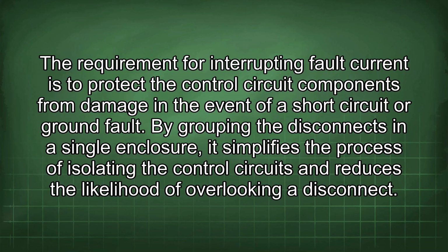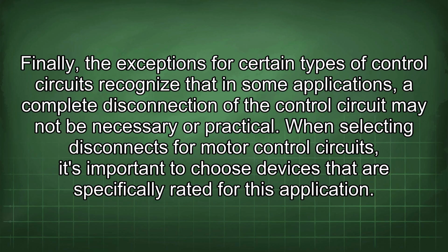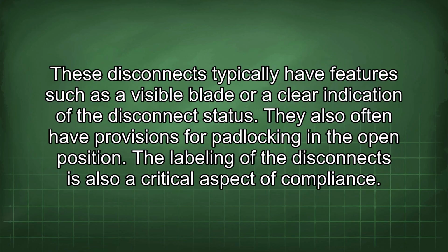By grouping the disconnects in a single enclosure, it simplifies the process of isolating the control circuits and reduces the likelihood of overlooking a disconnect. Finally, the exceptions for certain types of control circuits recognize that in some applications a complete disconnection of the control circuit may not be necessary or practical. When selecting disconnects for motor control circuits, it's important to choose devices that are specifically rated for this application. These disconnects typically have features such as a visible blade or a clear indication of the disconnect status. They also often have provisions for padlocking in the open position.